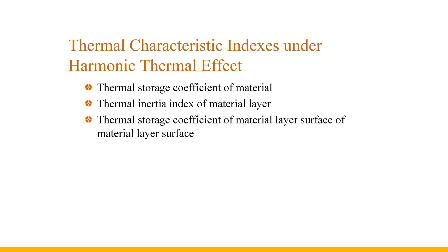Fourth, the attenuation and delay of temperature waves in the transmission process are caused by the heat capacity of the material and the thermal resistance of the material layer during heating and cooling. Fifth, when the thickness of the flat wall increases, the heat capacity increases and the thermal conductivity decreases, so the fluctuation amplitude of the inner surface decreases and the delay time of the maximum value is longer.